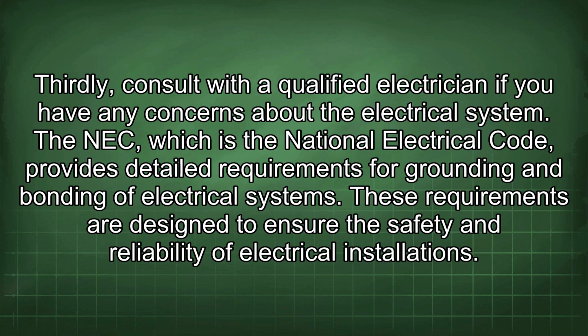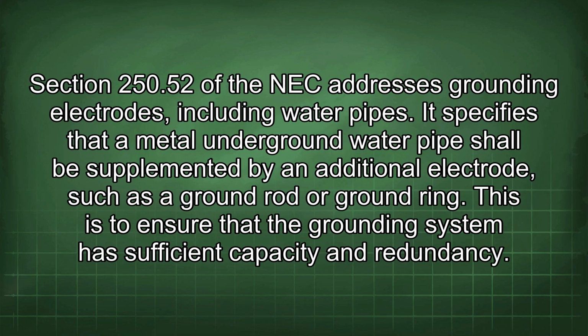The NEC, which is the National Electrical Code, provides detailed requirements for grounding and bonding of electrical systems. These requirements are designed to ensure the safety and reliability of electrical installations. Section 250.52 of the NEC addresses grounding electrodes, including water pipes. It specifies that a metal underground water pipe shall be supplemented by an additional electrode, such as a ground rod or ground ring. This is to ensure that the grounding system has sufficient capacity and redundancy.